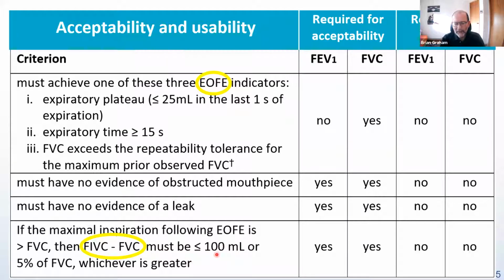The limits being put in are the same criteria as for the back extrapolated volume. You must be within either 100 mils or 5% of VC. And that's required for both FEV1 and FVC acceptability. If you don't do this maneuver, it doesn't negate the acceptability, but this becomes a really important internal control of the acceptability of the maneuver. I'll talk a bit more about that in a second.